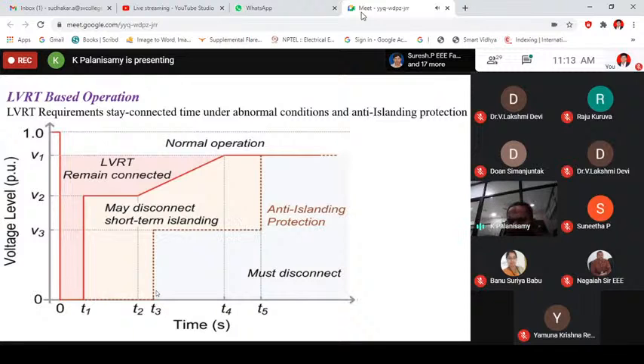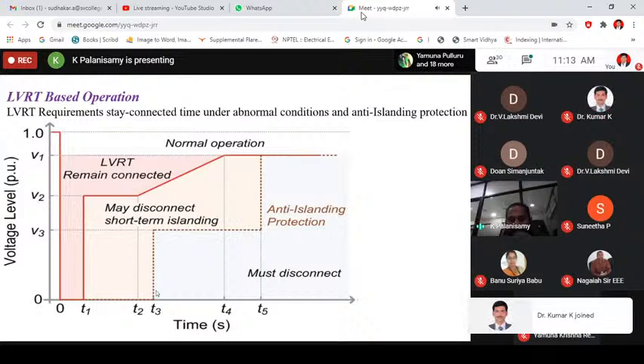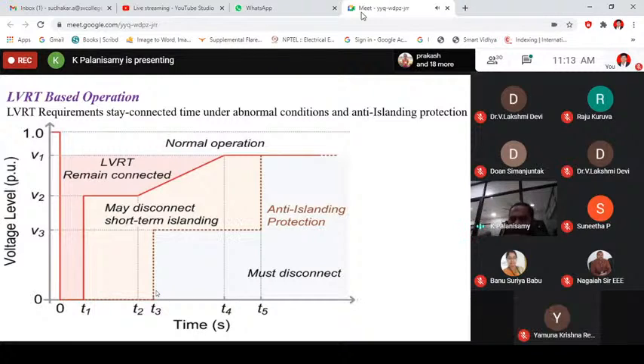If the voltage goes less than 360, the windmill or wind generator connected to the system will get disconnected. There's a control in such a way. If the voltage goes below 360 volts, with the rated voltage being 400, it will isolate. It means your generation is removed. So like this, there will be cascaded switching off of windmills.